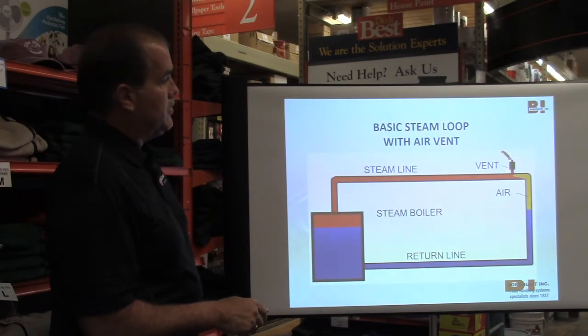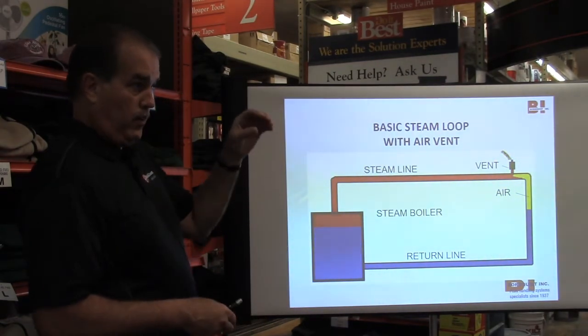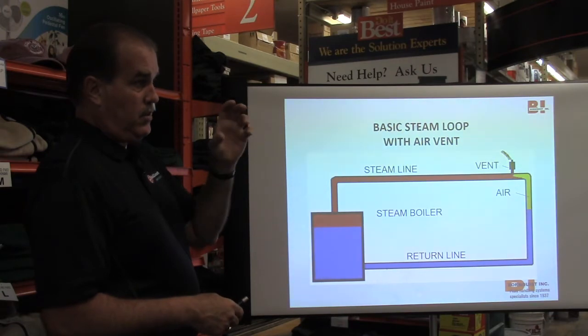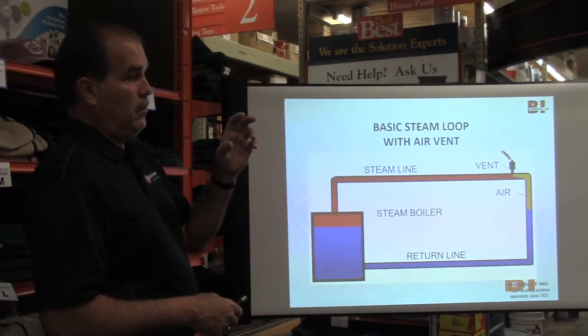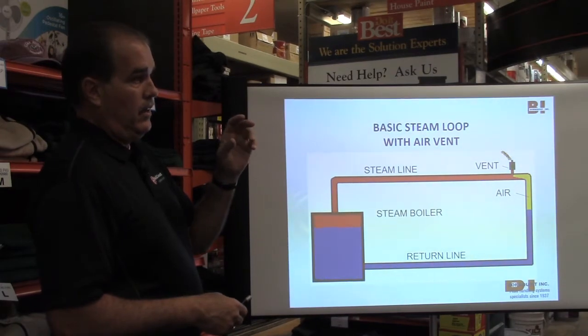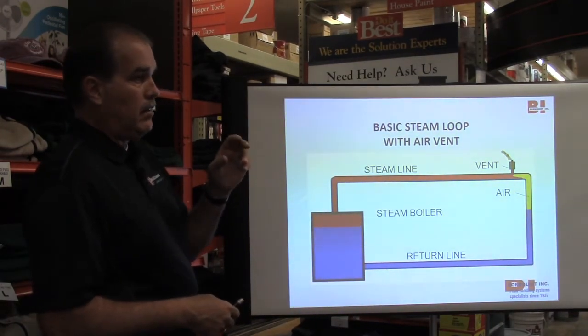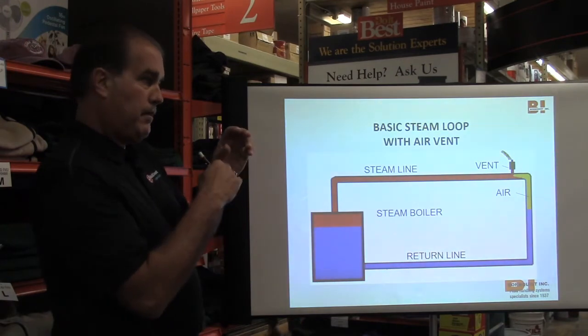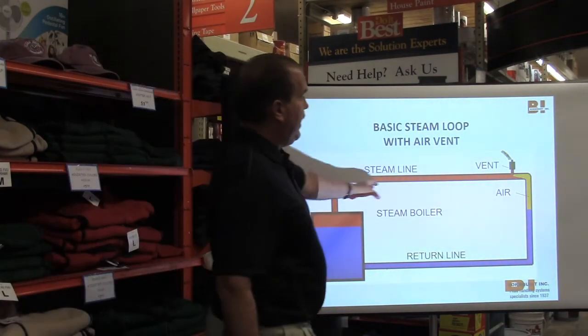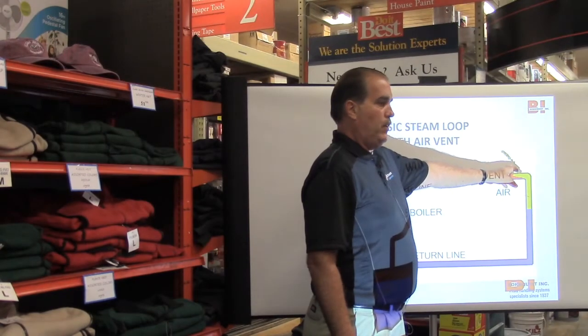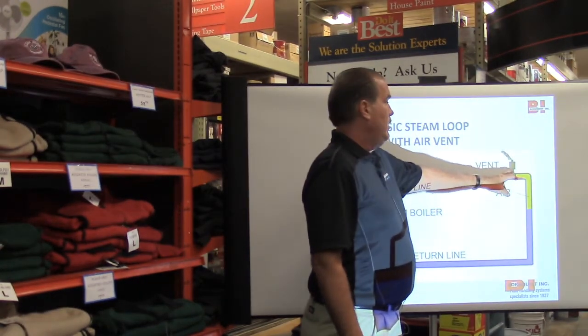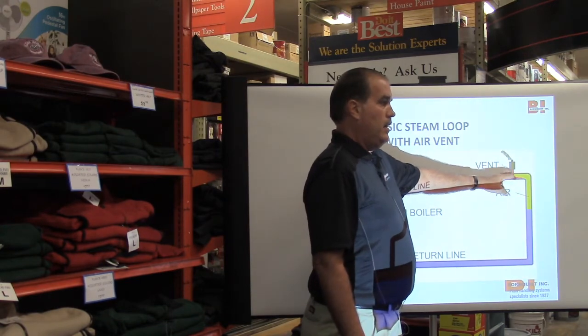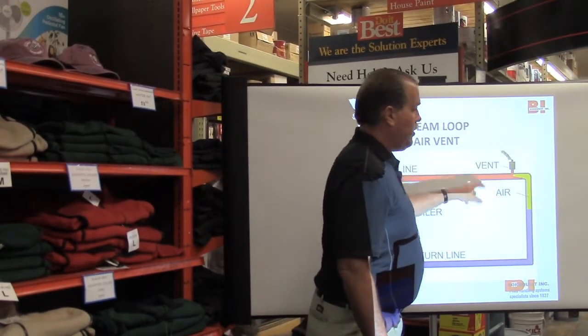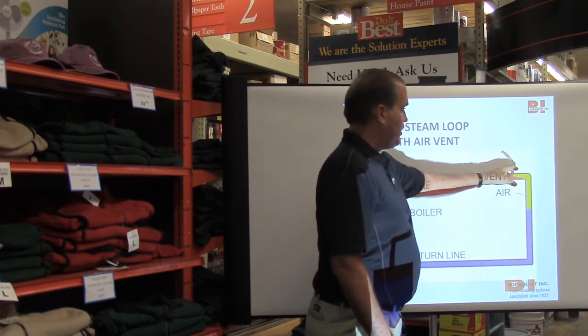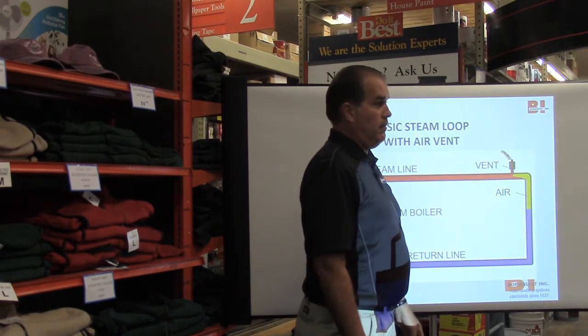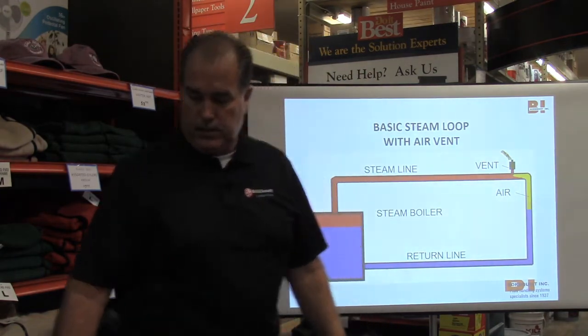Because what happens in here is there's a little float for water, so if water gets in it, it's going to shut off. But the float is also filled with an alcohol mixture. As it heats up, the alcohol expands, and there's a little diaphragm at the bottom of the float. When there's just air, it's too cold, so the float won't expand. However, when steam gets to it, it expands and shuts off. In the meantime, while it's just air, it's getting rid of the air. You don't want air in your system. But once the steam hits it, you want it to shut off because you want to save your steam. And that's how a steam vent works.